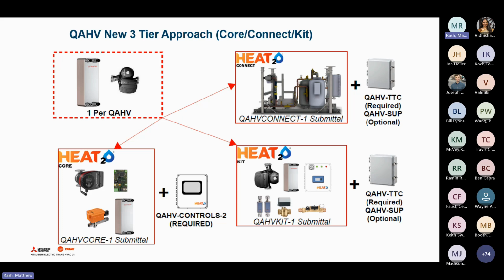And then depending on the application, we have different options for how that pump heat exchanger boundary is controlled with regard to flow turn down on the potable side, to what degree of flow turn down we can get to, as well as other enhanced capabilities for COP monitoring. So right here in this diagram, this is what we call the primary side, and the secondary side with storage. Those are components that we control with this solution, meaning we want you to purchase and procure those from us because they're critical to how the product is applied. The swing tank is going to be procured locally or by others, by the installing contractor. There is some flexibility on the storage tanks. For storage tanks that are farther upstream, I'm referring to the hot tanks, but the cold tanks, the temperature control tanks, we always want those procured from us.